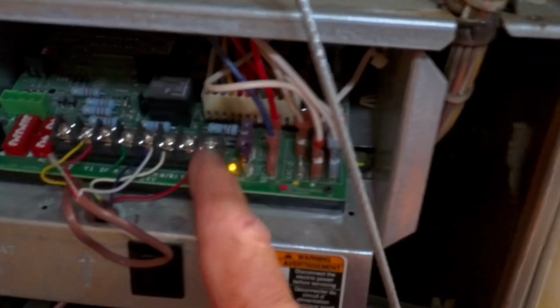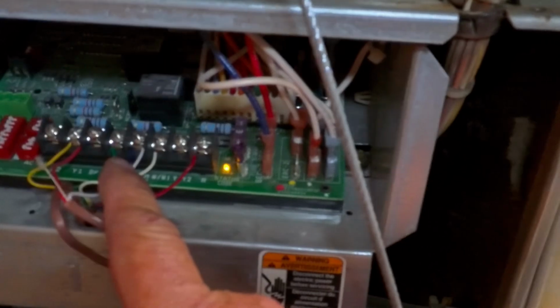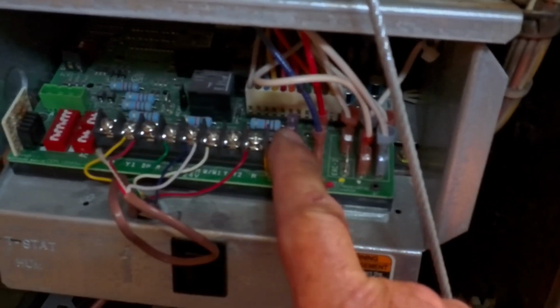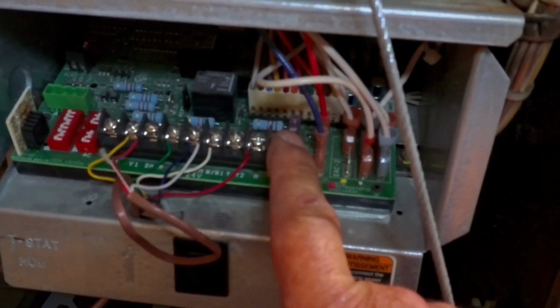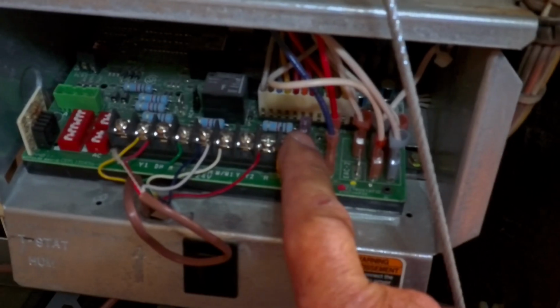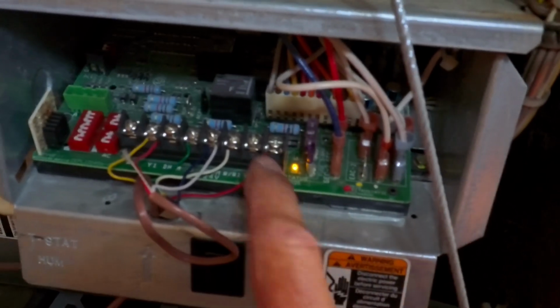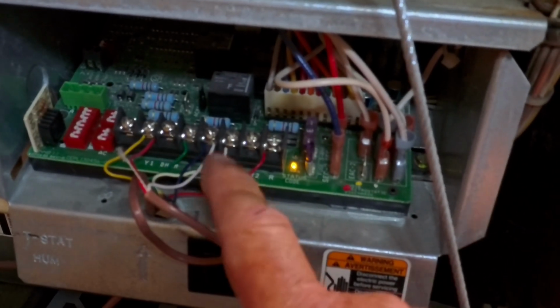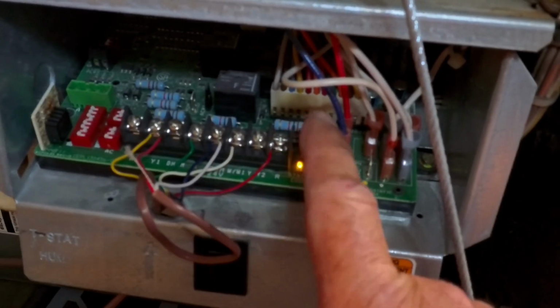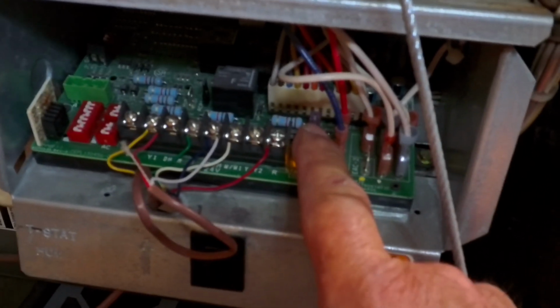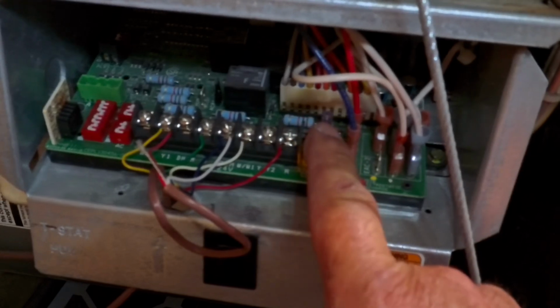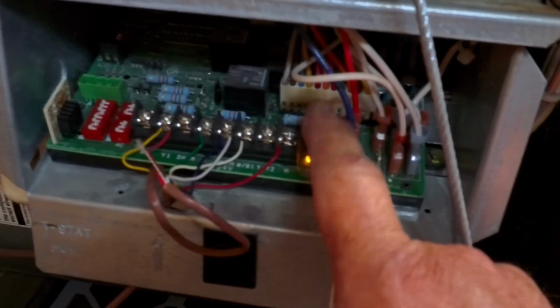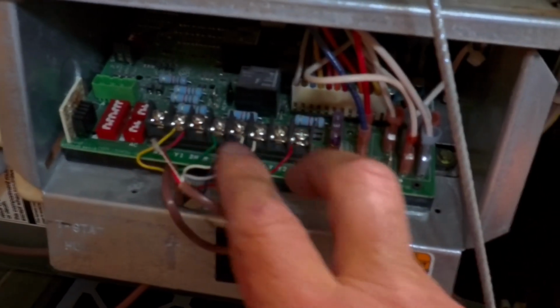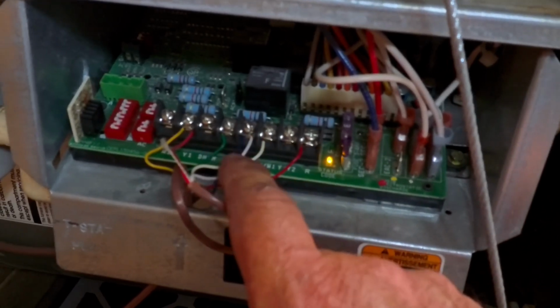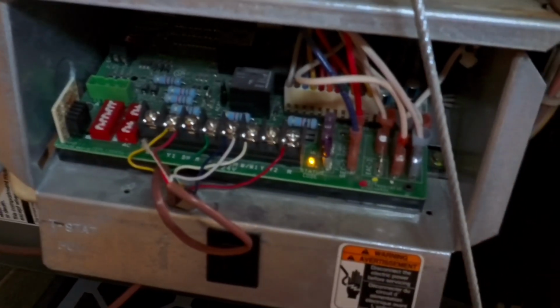Now if we did not have voltage or 24 volts across the R and the C terminals, the first thing I'm going to look at is this little 3 amp fuse right here. It's an automotive style fuse, and the job of that fuse is to protect the transformer in case something gets shorted out in the low voltage system. It's going to blow that fuse before it smokes our transformer. We'll get more into that when we get into the outdoor unit troubleshooting. But for this scenario, we have 24 volts across our R terminal and our C terminal. So now we need to move on to the next step.